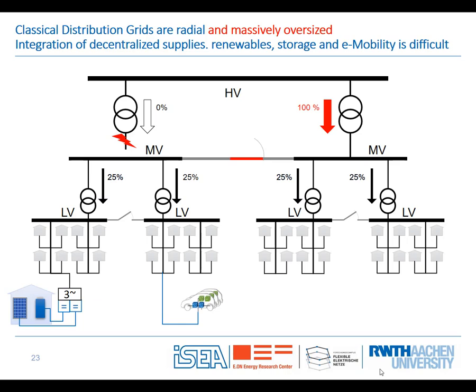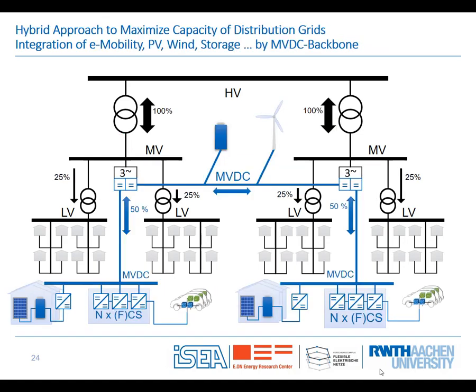Actually, I hear from most utilities that their transformers are on average never used more than 30% of installed capacity, which is why they've eliminated blowers and cooling systems over the years. So there's a lot of spare installed capacity. If we interconnect the medium voltage substations with medium voltage DC—or low voltage, there's still debate on what's best—then I can always draw that 50% overcapacity through the DC bus from one substation to the other, creating this interconnection.